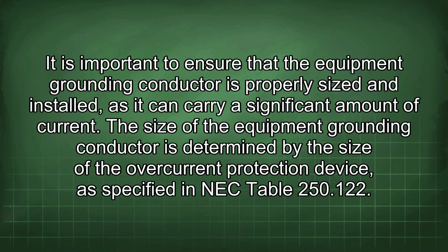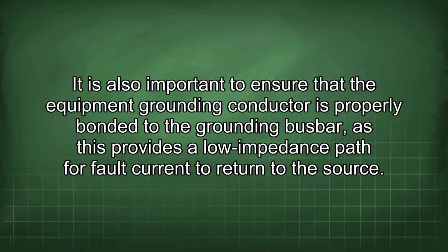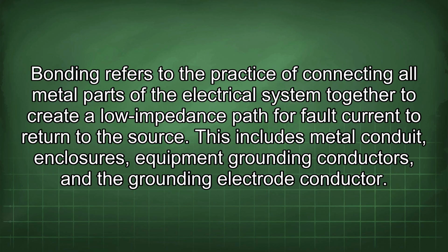The size of the equipment grounding conductor is determined by the size of the overcurrent protection device, as specified in NEC Table 250.122. It is also important to ensure that the equipment grounding conductor is properly bonded to the grounding busbar, as this provides a low impedance path for fault current to return to the source. Bonding refers to the practice of connecting all metal parts of the electrical system together to create a low impedance path for fault current to return to the source. This includes metal conduit, enclosures, equipment grounding conductors, and the grounding electrode conductor.